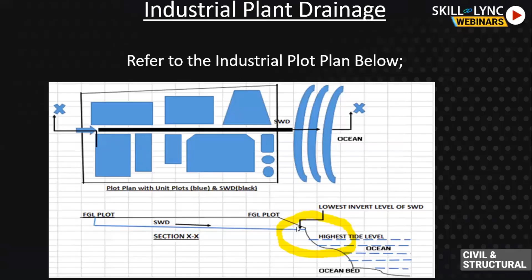So that way the road crossings are required to be designed, and then they are disposed, as I told you, either in sea or in raw water, fire water pond. The hydraulic design calculation I told you, that 1 upon n R raised to 2 by 3, that formula we have to use. We have to find the invert levels. And again, here at the starting point, the invert level, that is depth below the ground level, this invert level will be highest. This will be the high point, and there will be the slope, and the end will be a low point.